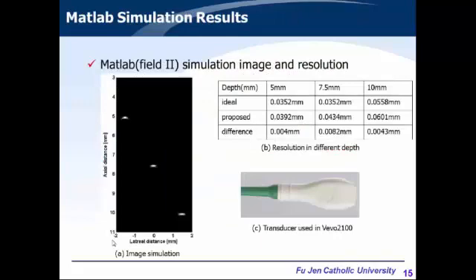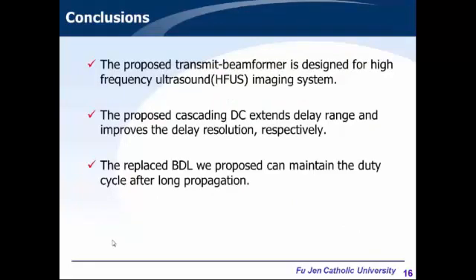This is a Matlab simulation using Field II. Our design can make the transducer focus on different focal points at 5, 7.5, and 10 millimeters, and the resolution is shown on the right side. In conclusion, the proposed transmitted beamforming is designed for a high-frequency ultrasound imaging system. We use cascading delay cells to achieve wide range and improved delay resolution. The proposed delay line design can maintain duty cycle after long propagation. Thank you for your attention.